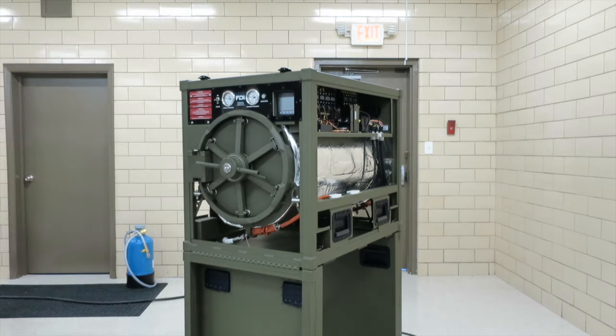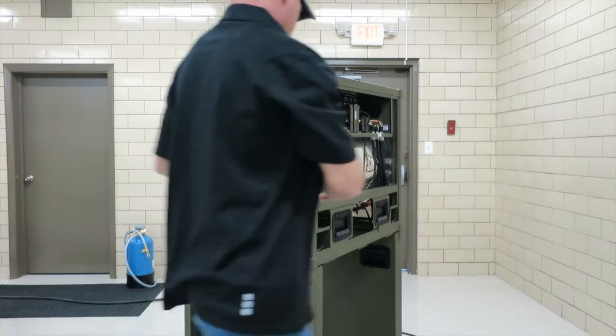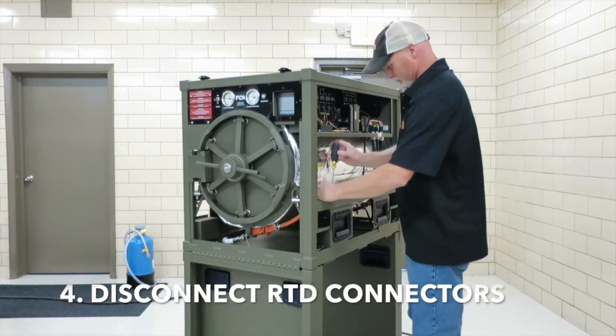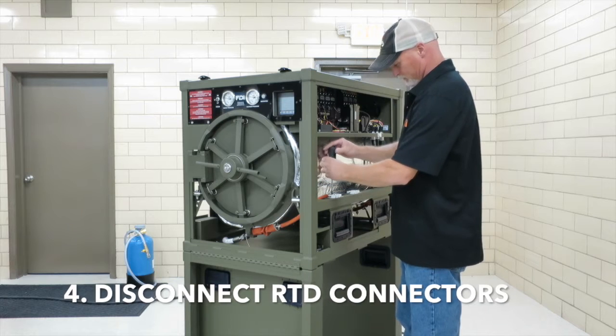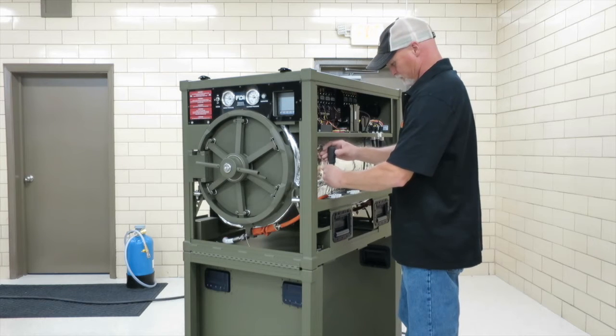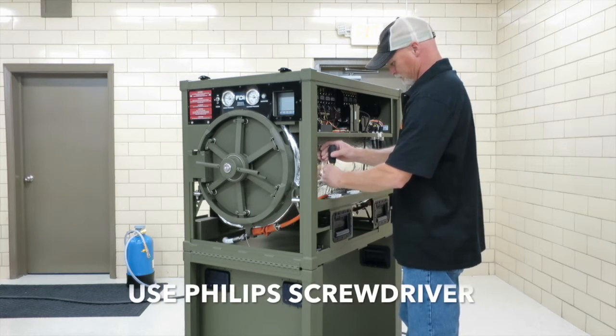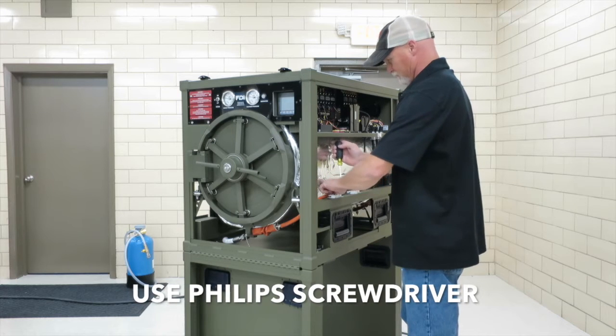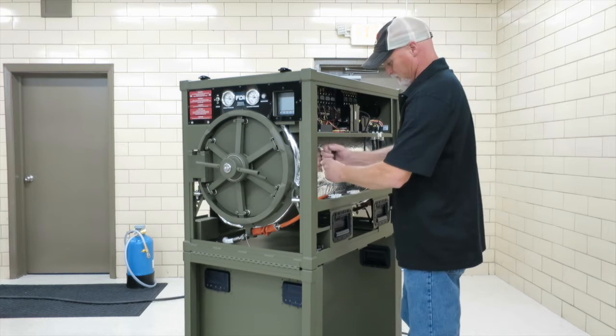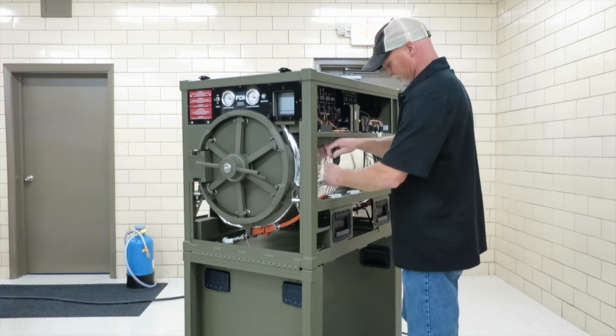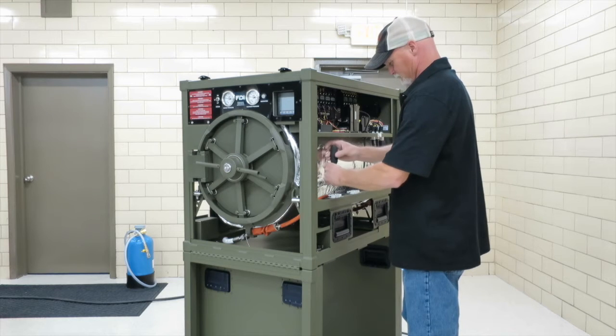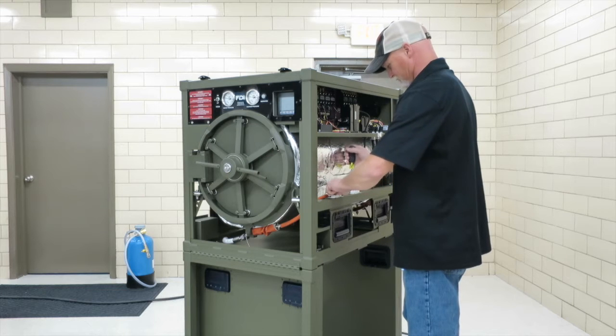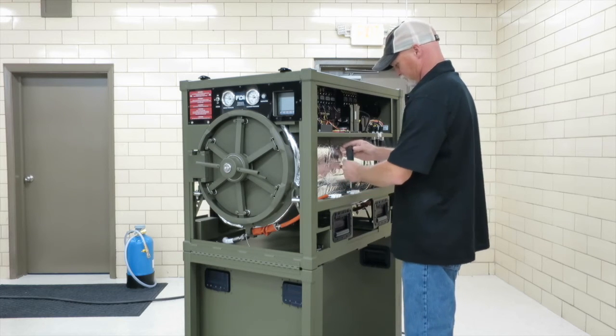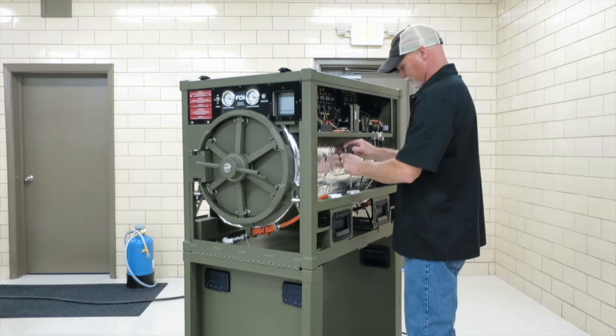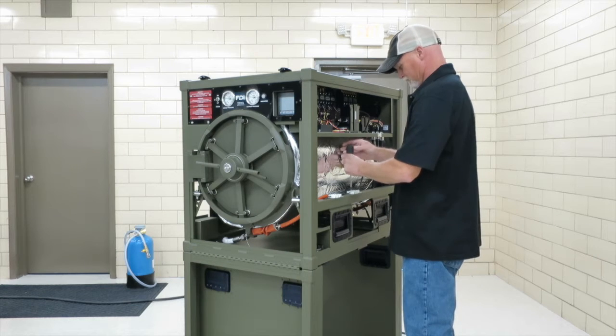So next we're going to disconnect the electrical connector. We're going to take the screws out of the left side only. The right side, you can leave those in. That's connected to a cable that goes up to the RTD transmitters. So we just need to take the 2 screws out of each of those connectors. There's 2 different connectors because there's 2 different elements, RTD elements, inside the probe. We have RTD1 and RTD2, so both of the left-hand portion of the connectors need to come off.